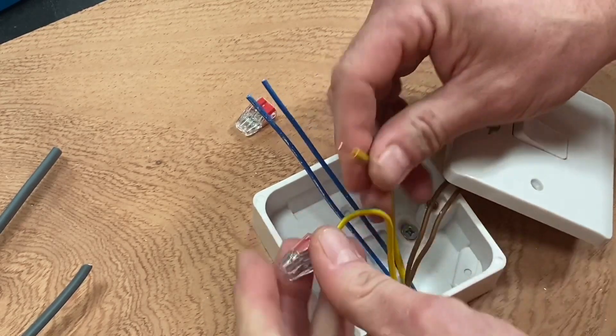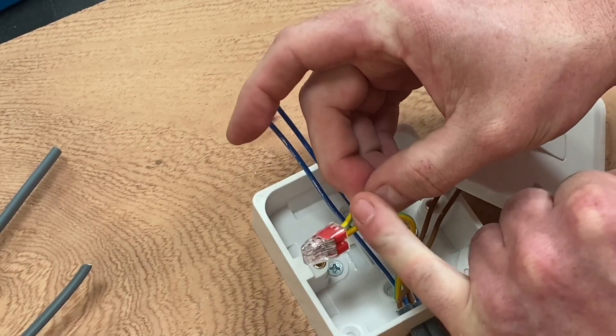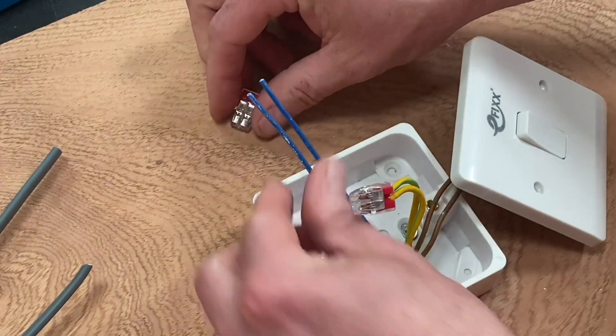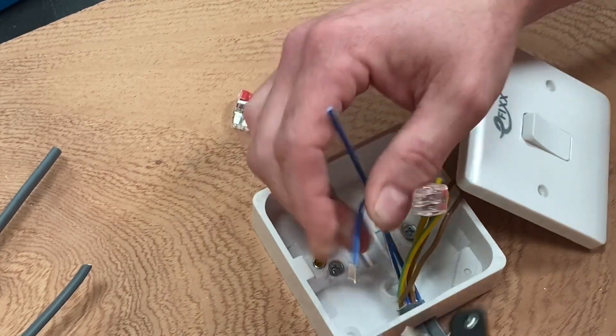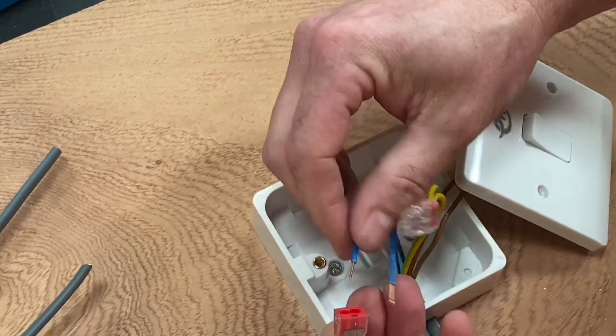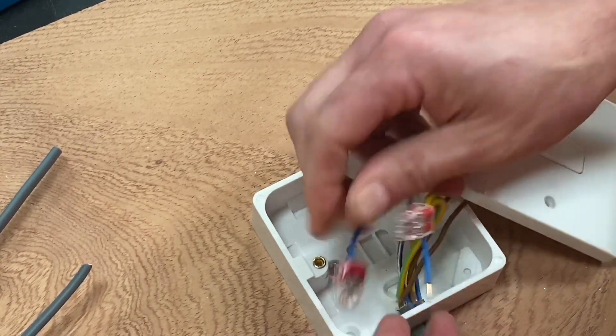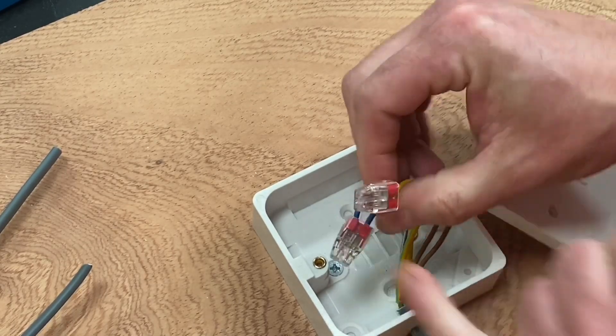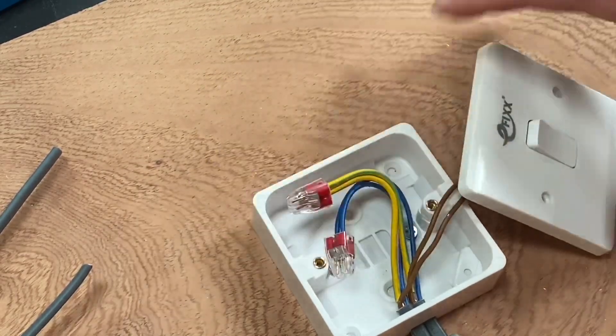Like so, nicely see it there in the window, connect the other one. It's worth really gripping onto the actual conductor itself, not just the sleeving, because it can feel as if it's moving. So they're in nice and secure. Just got to do the same now for the neutrals. Remove the required amount of insulation and then just simply again just push them into there like so. And we can clearly see again our conductors are connected into the enclosure itself, so we can leave those in there and then obviously we can put our light switch cover back on.